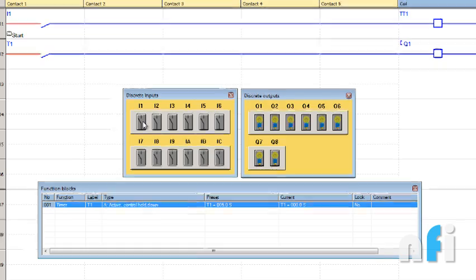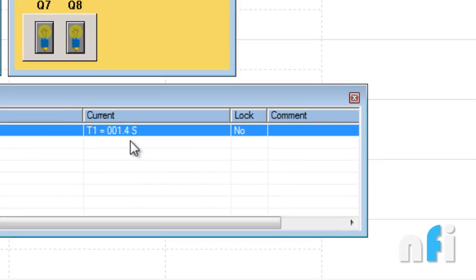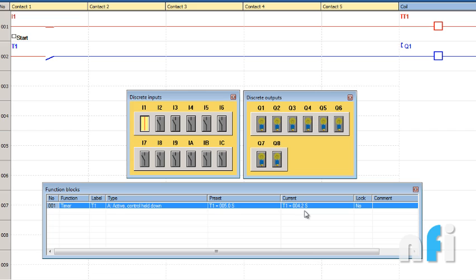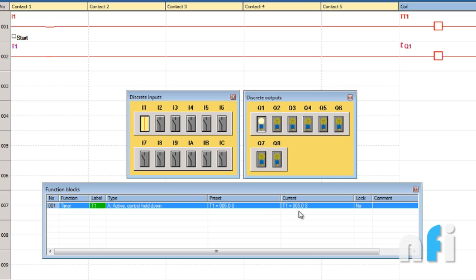Let's run this. I'm going to press I1. You'll find timing starts here - three seconds, four seconds, at five seconds output is on. If I release I1, the timer gets reset. The accumulator is not equal to five, so when this time becomes equivalent, the bit gets on. I'll show you again - pressing this input, timer is activated, starts counting the time, and after five seconds they become equal, T1 is true, this is getting on and turning on the output.